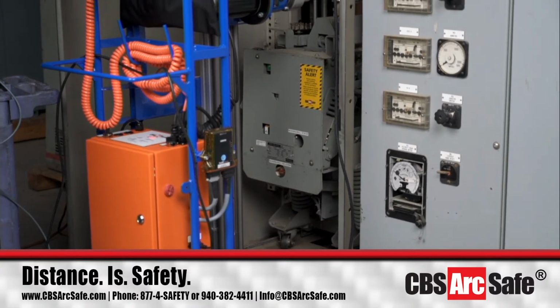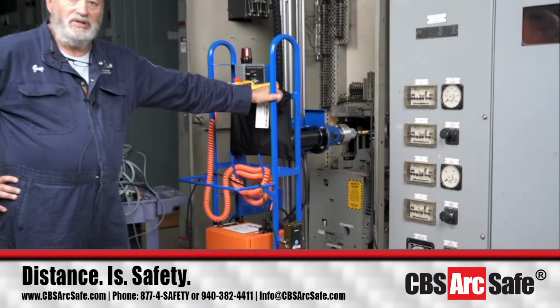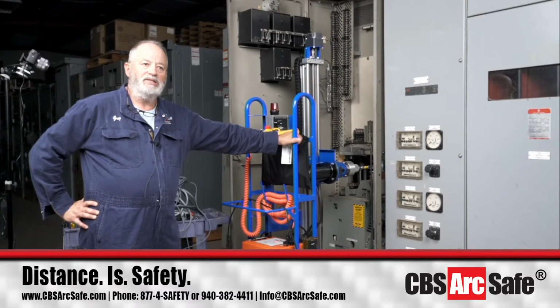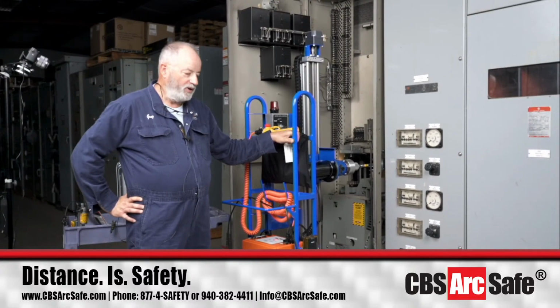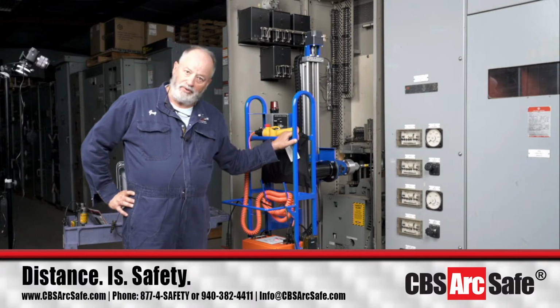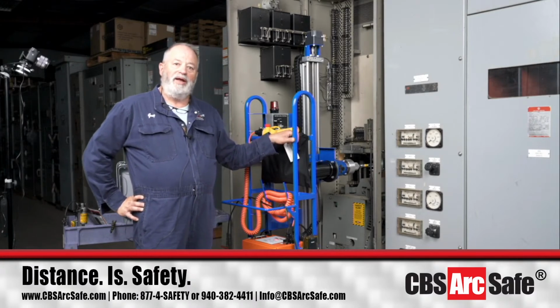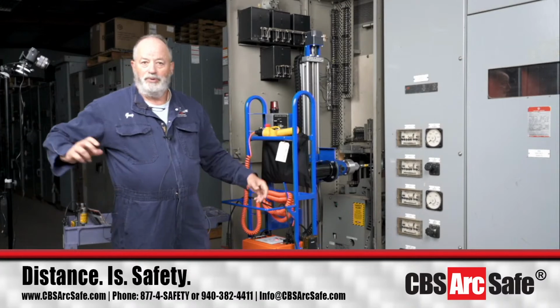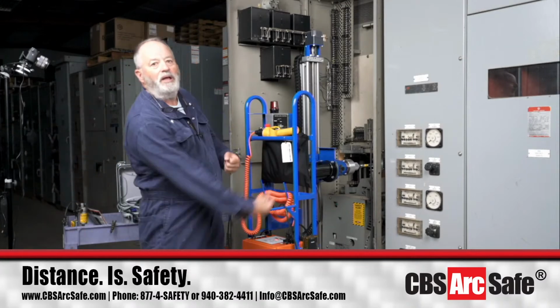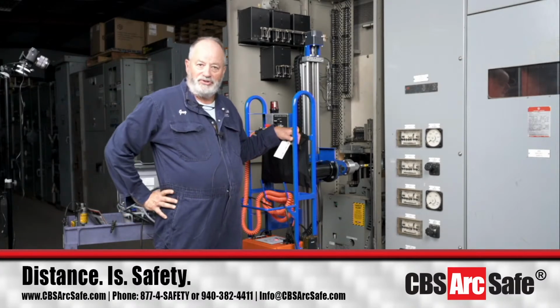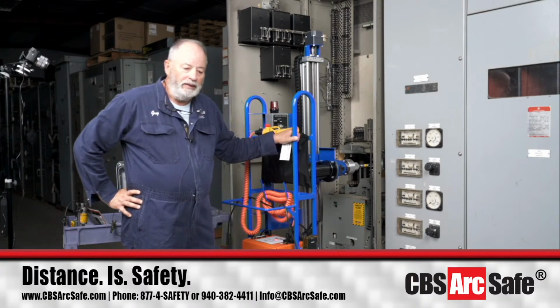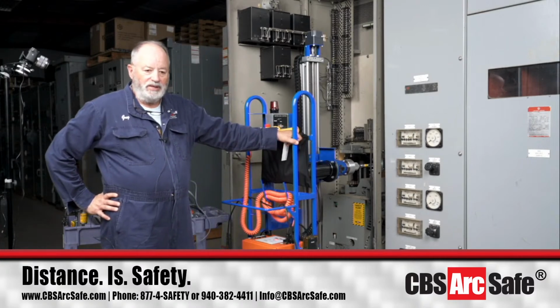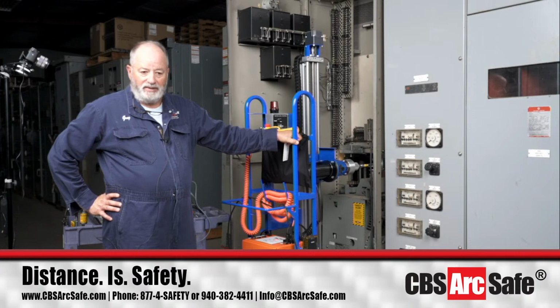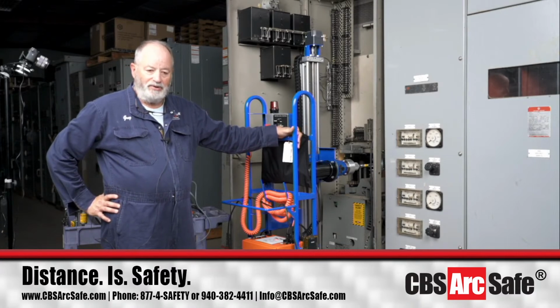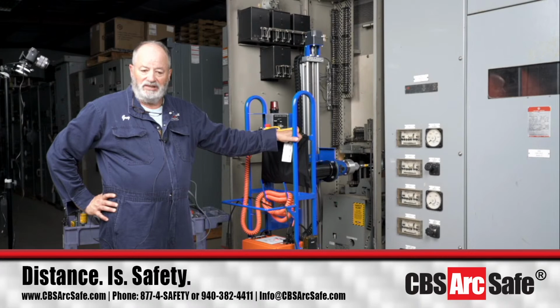And I can give you an example. Two times in the domestic United States, I've run into breakers where I had to use the brute force mode of an RS1 to get a breaker out, because some guy had put this in and then he got to the end and went, ugh, and went that extra oomph just to show that he could put it in more. And normally, like a PAL-VAC should take about an install value of about 18 on an RS1 and a remove value of 15 to 16.